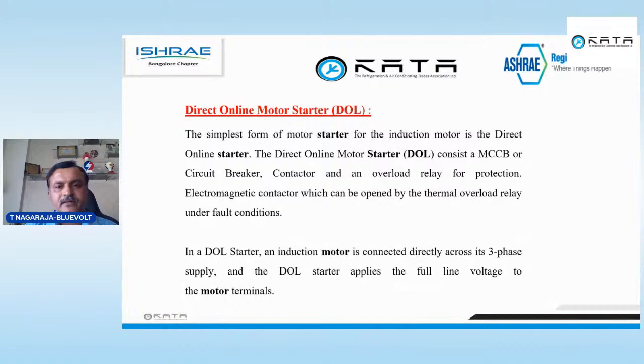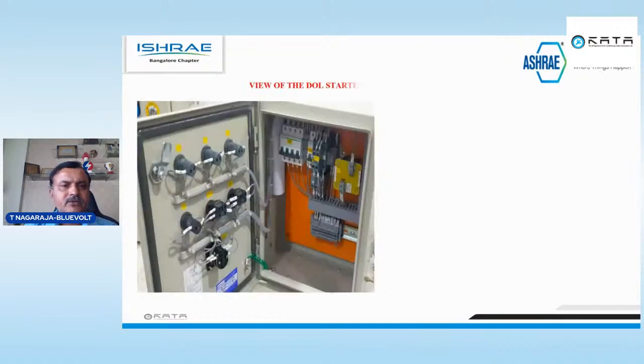Beyond 5.5, or from 7.5 onwards, it will be a star delta, because of the power fluctuations or inrush current of the motor. But in power plants they go even to 200 kilowatt with DOL starters, because they have enough power within their premises itself. They are the manufacturers, so they go even to 200 kilowatt with DOL starters. So up to 5.5 kilowatt, we use a DOL starter.